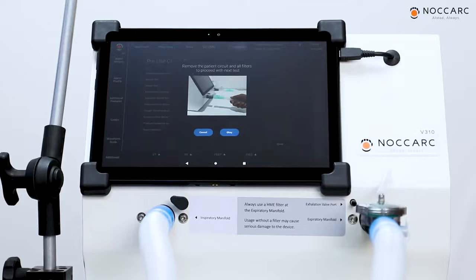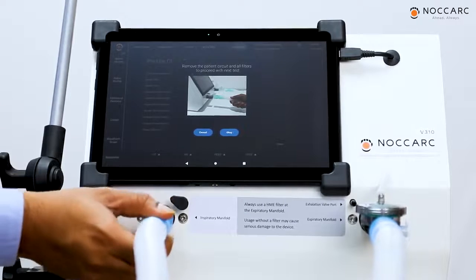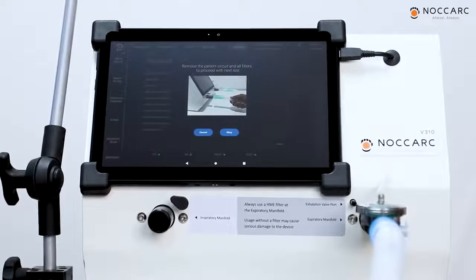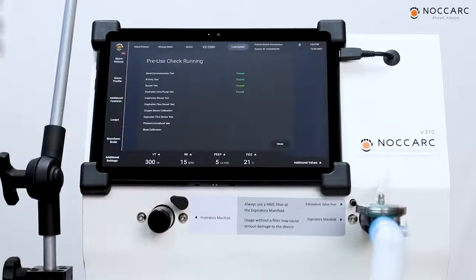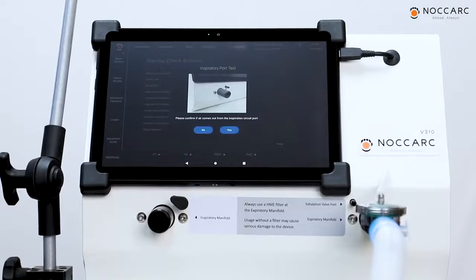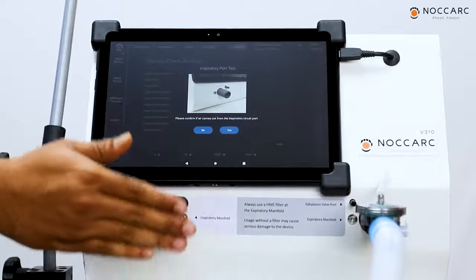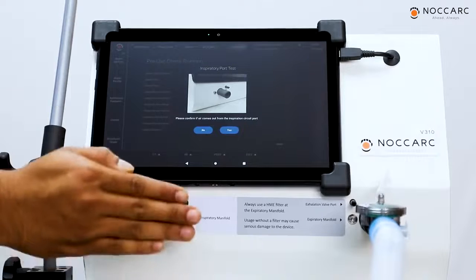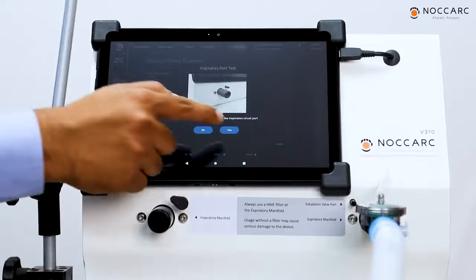Now we have to remove the circuit and all filters to proceed to the next test. I will remove the patient tube from inspiratory, and we have already removed the HME filters from the ventilator. So I will press OK. Please confirm if air comes out from the inspiratory circuit port. So from inspiratory, I can feel that air is coming out. So I will press yes.